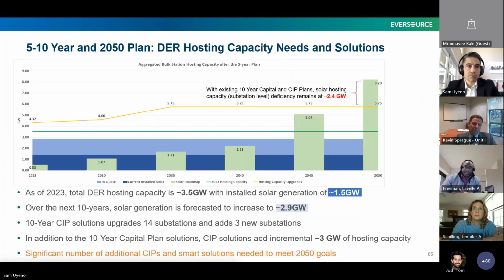Next slide. On this slide, I'll spend a little time trying to answer Russ's question, not too much since we want to get to Jennifer. This slide illustrates the hosting capacity due to the proposed investments. As of 2023, the total DER hosting capacity is 3.5 gigawatts, shown by the green horizontal line on the chart. There's currently 1.5 gigawatts of installed solar, shown as the dark shaded area at the bottom. This is less than the hosting capacity at a macro level, which is a good thing, so we have sufficient hosting capacity for the solar we've installed.